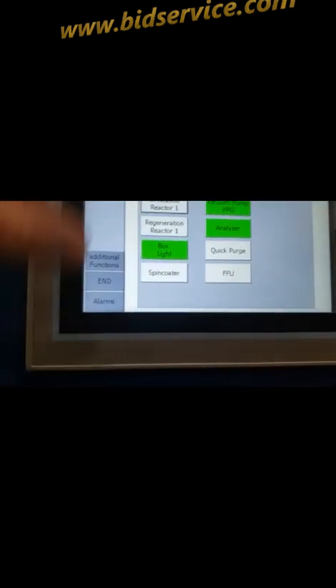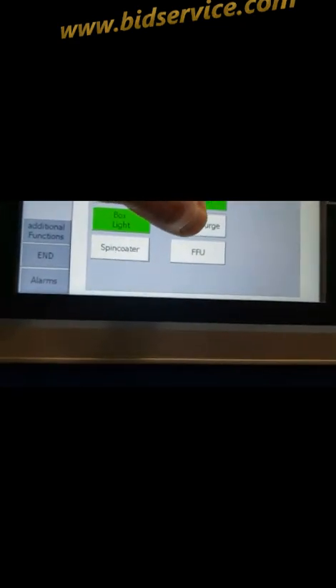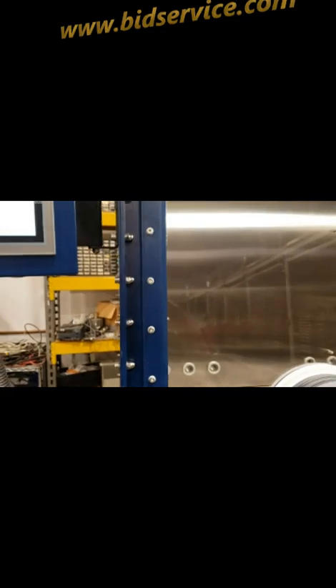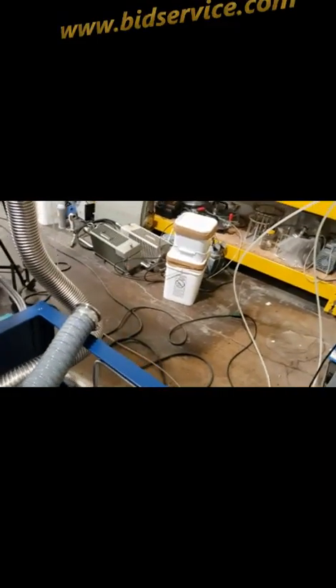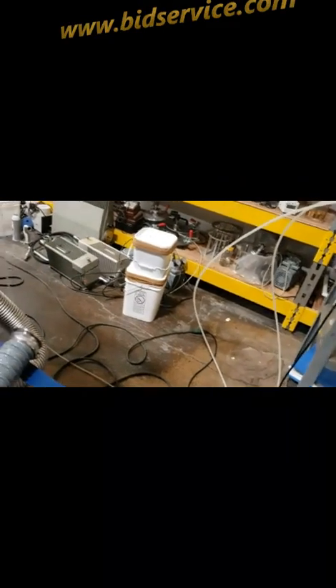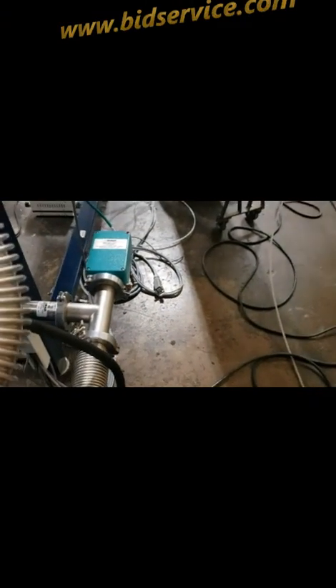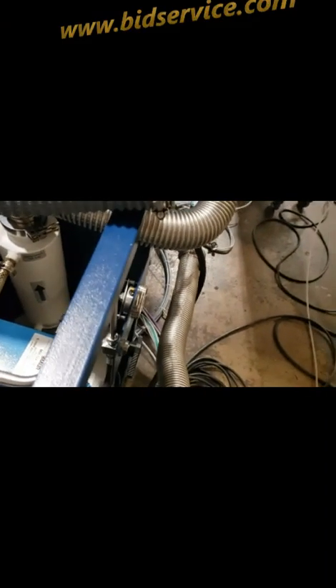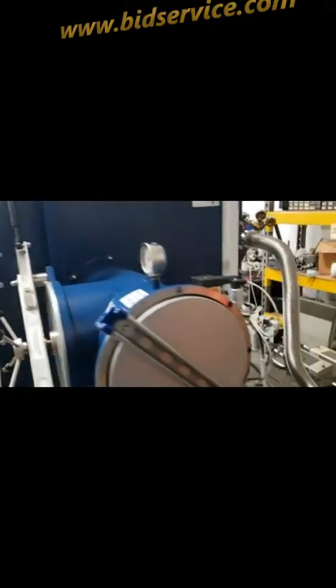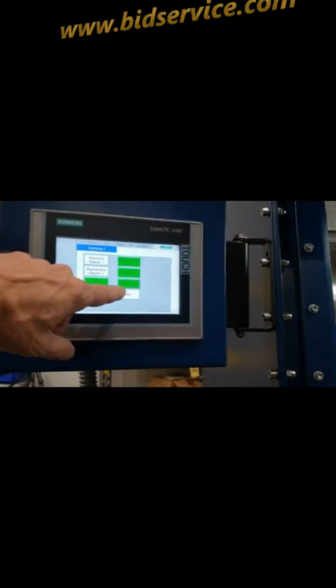When you want to do a regeneration, you have to shut your circulator off first and then go through the regen process by hitting that. I'm not going to do that right now. The other thing you can do is hit the quick purge. What that does is open up this valve here, and it purges through this line here. So the purge will go through the circulator, goes in the opposite direction. It'll go out through this line here, and then return on the bottom line across the moisture sensor through the solvent trap, and back. And that's to remove any excess oxygen or water vapor that may have occurred at any certain time. You can also use this to do your initial purge of the box.